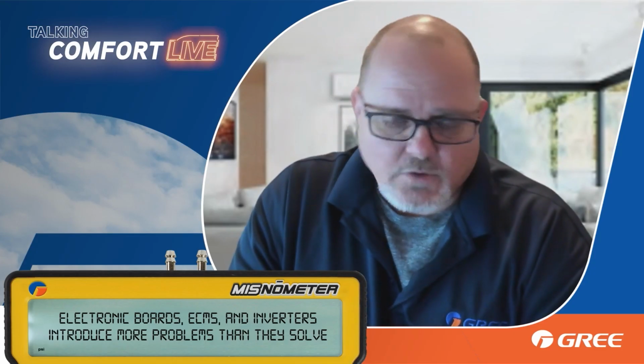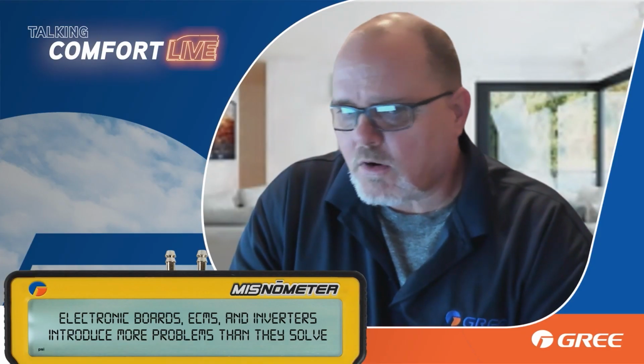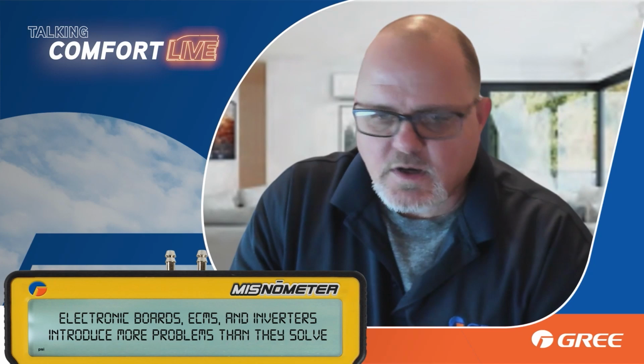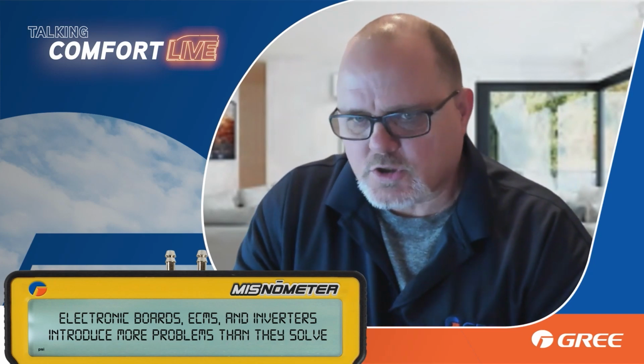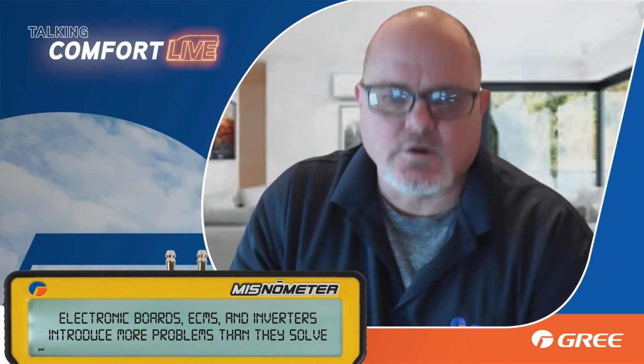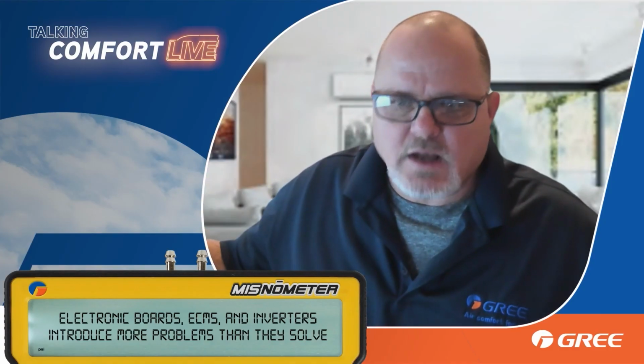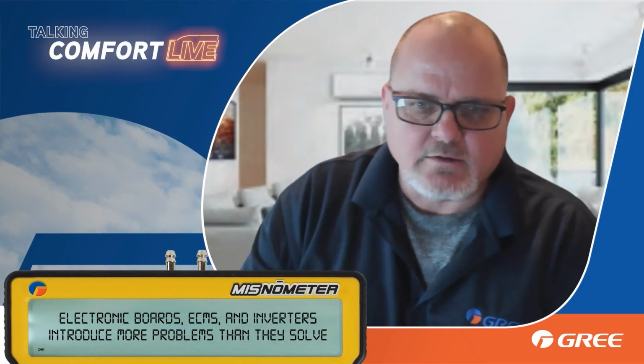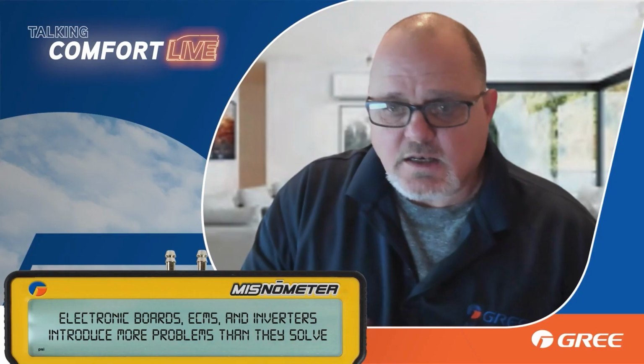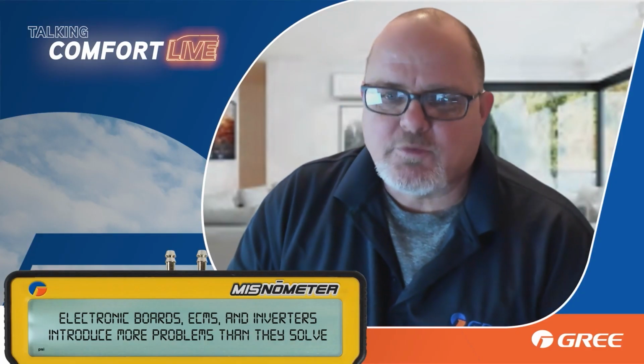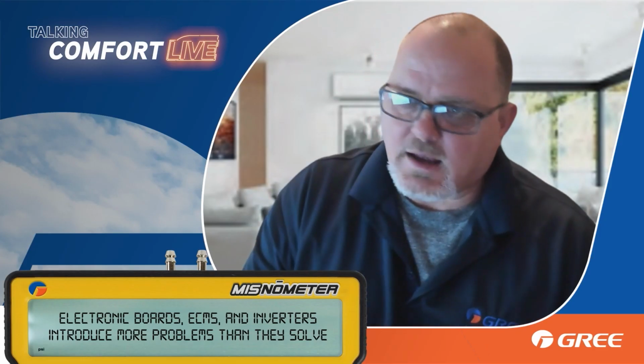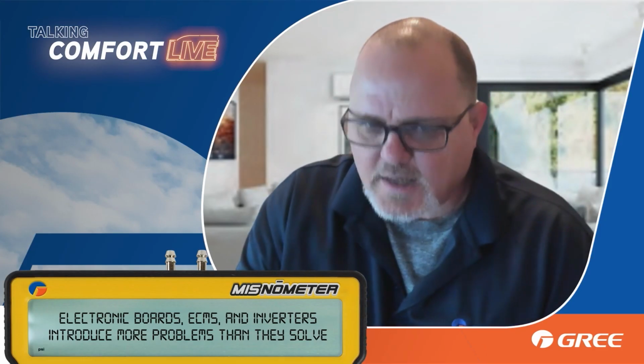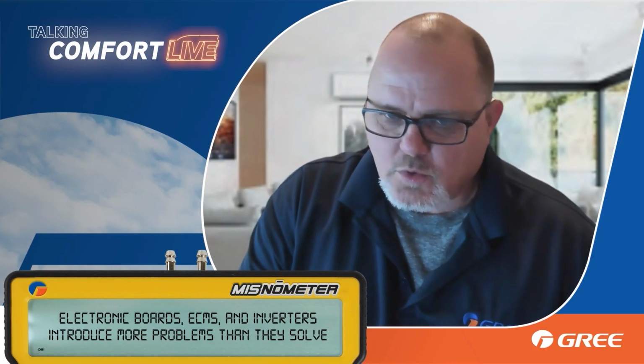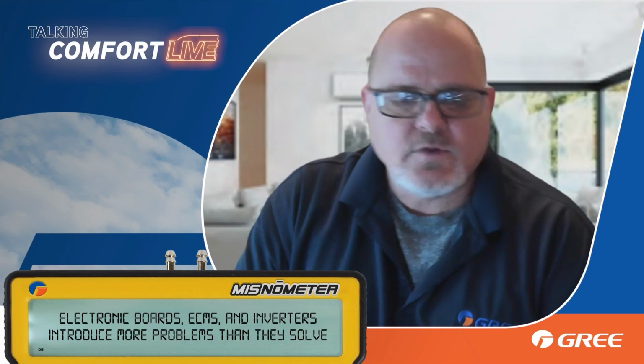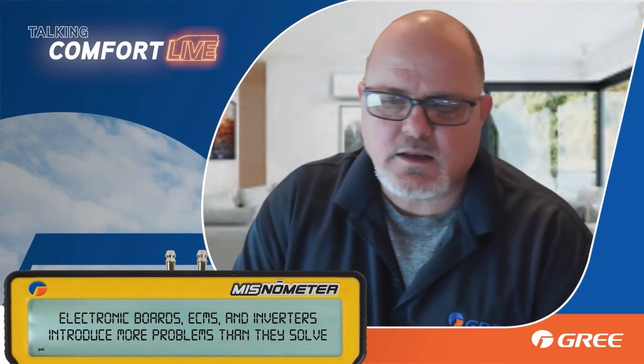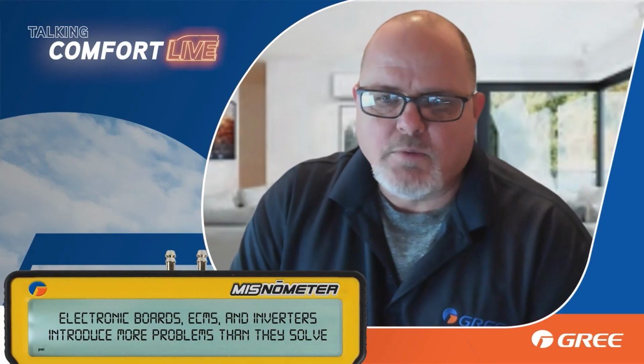I've even seen it on the multi-zone mini split where the range was so far off that one circuit would never function. The other circuits will function. So let's say it's the A circuit. For whatever reason, I can't ever get any cooling out of the A circuit, but B, C, D, and E work fine. And then when they do their checking, they find out that the A circuit's got a bad thermistor in it, not electrically open or shorted, way out of range, that the board doesn't know what to do with it, so it never allows refrigerant flow to that head. The indoor fan runs, but your EEV's outside in that condenser. It just never lets the EEV open, lets it flow.